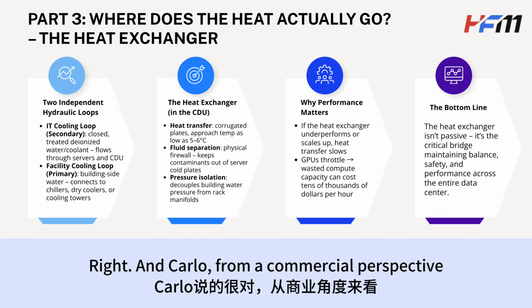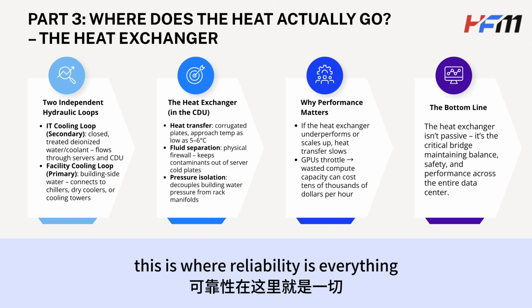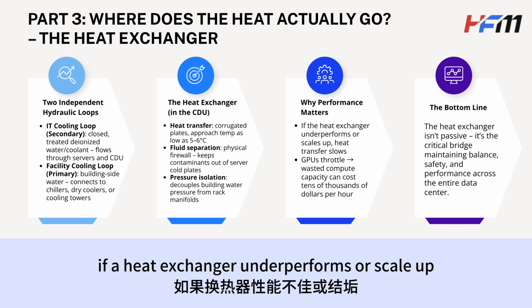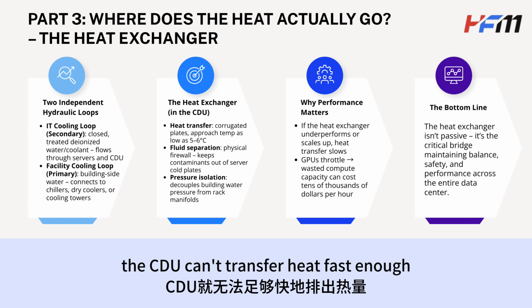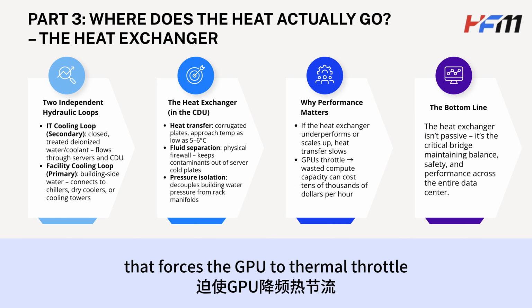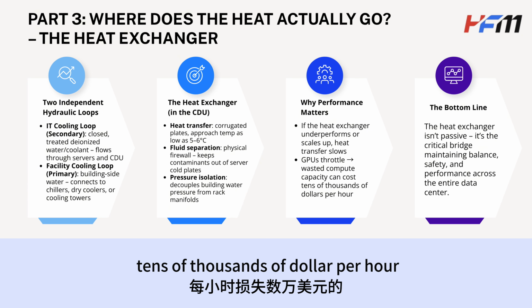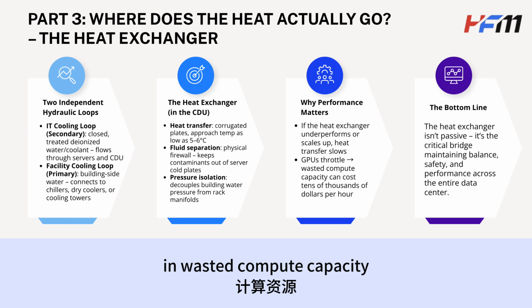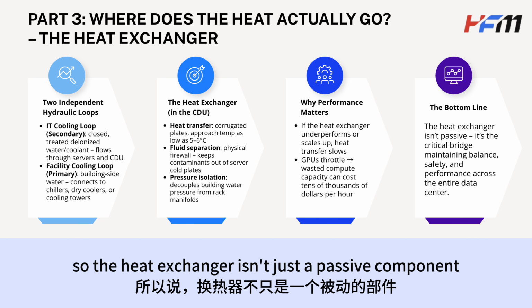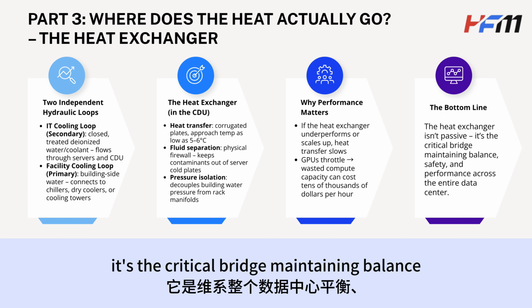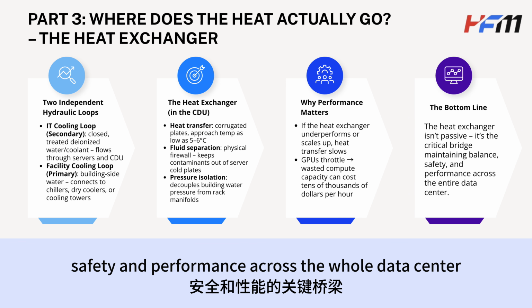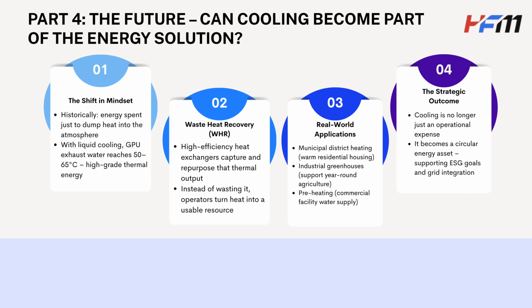Right, and from a commercial perspective, this is where reliability is everything. If a heat exchanger underperforms or scales up, the CDU can't transfer heat fast enough. That forces the GPU to thermal throttle, which can cost the operator tens of thousands of dollars per hour in wasted compute capacity. So the heat exchanger isn't just a passive component—it's the critical bridge maintaining balance, safety, and performance across the whole data center.